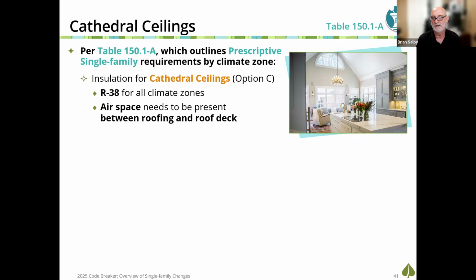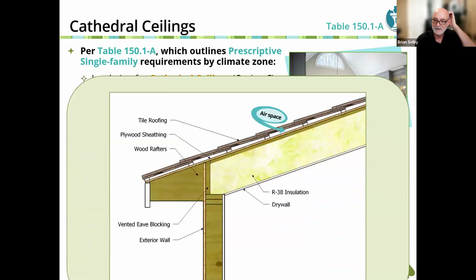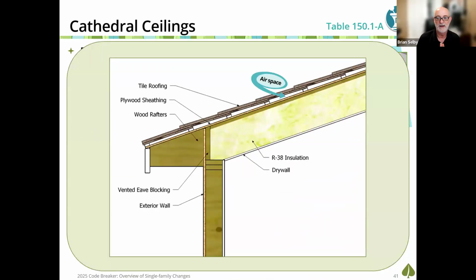Insulation requirements meeting option C: a non-attic roof needs to meet at least R38 cavity insulation in all climate zones. Now, keep in mind there must be an air space between the insulation and the roof deck when that insulation is installed, not only prescriptively to meet the roofing material requirements, but also to meet the building code requirements.